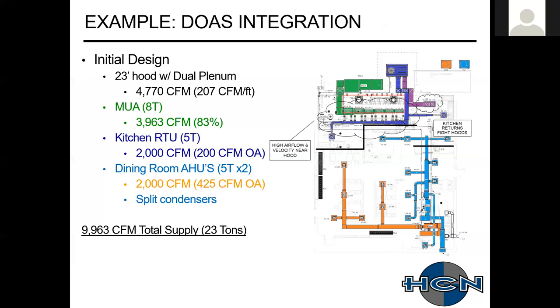Here's an example of an integration a colleague of mine worked on in Nashville, Tennessee. Initial design was a hood system with the dual plenum configuration, a dedicated makeup air unit, a rooftop unit, and a couple splits, I believe, and air handlers in the space. So the big thing here is 9,000 CFM of total supply air, 23 tons. It's a kind of closed off kitchen design.